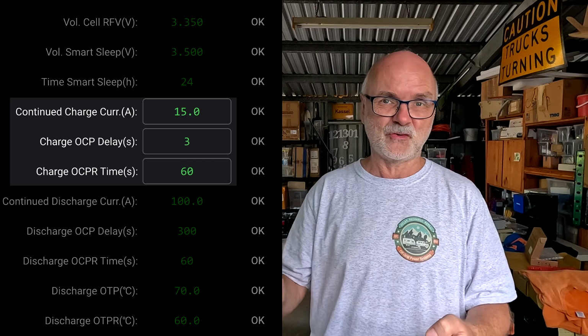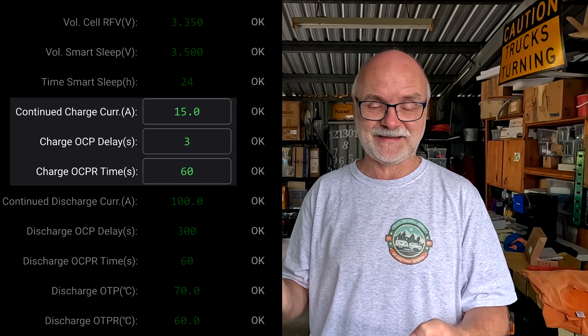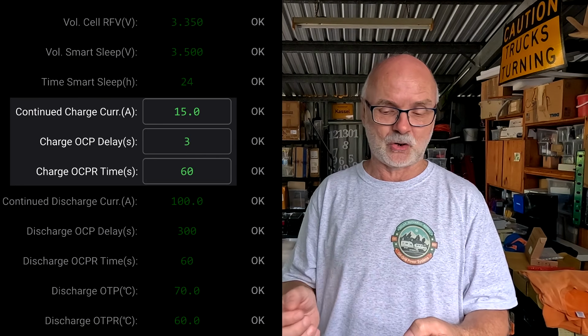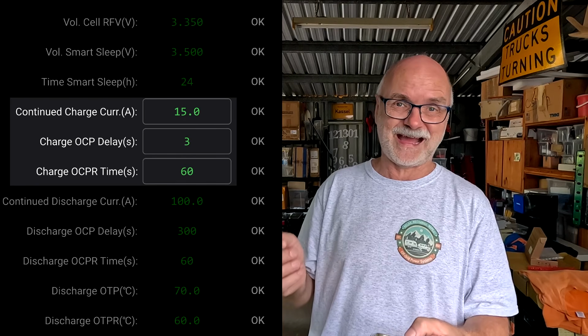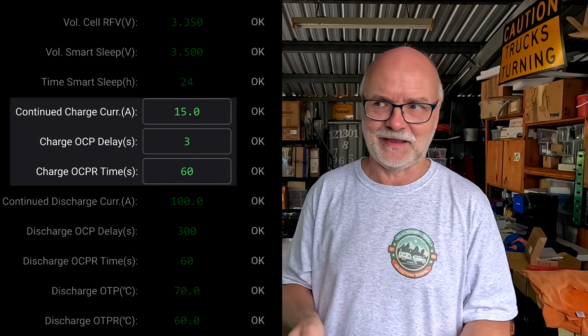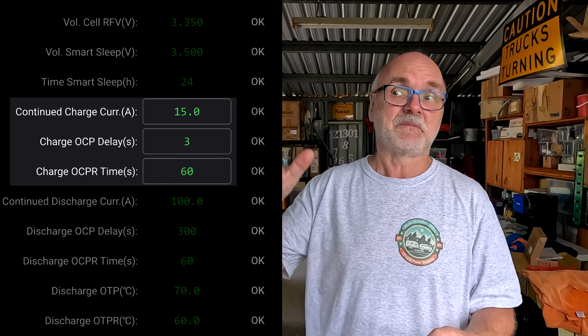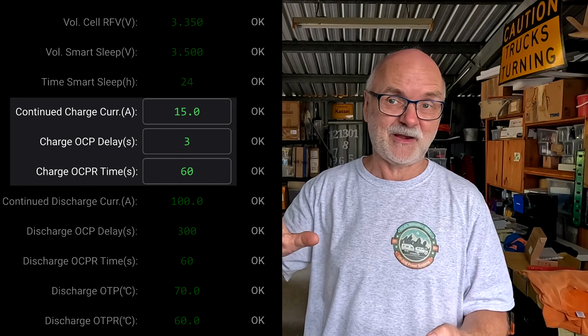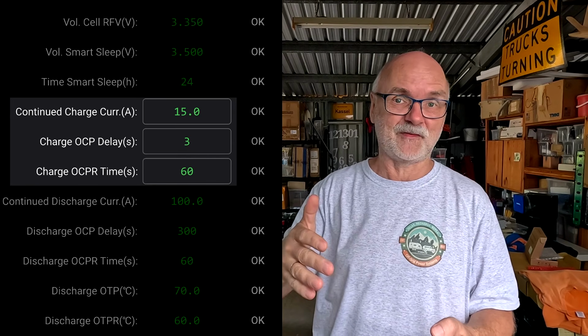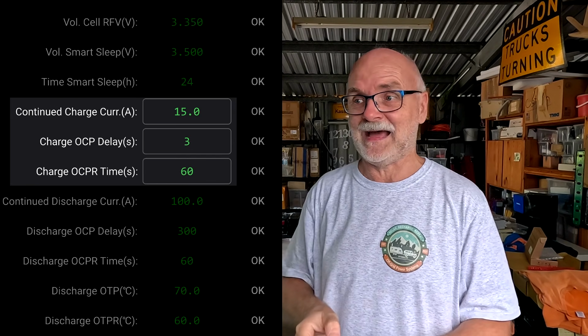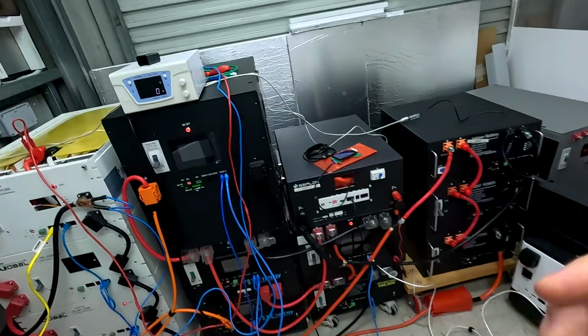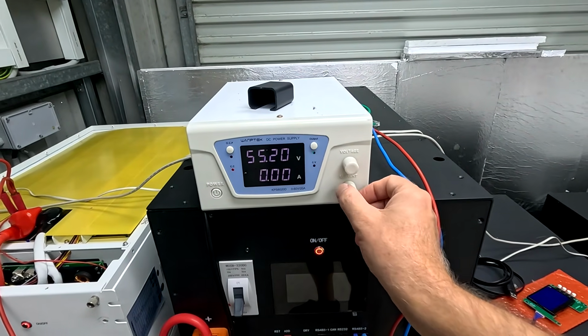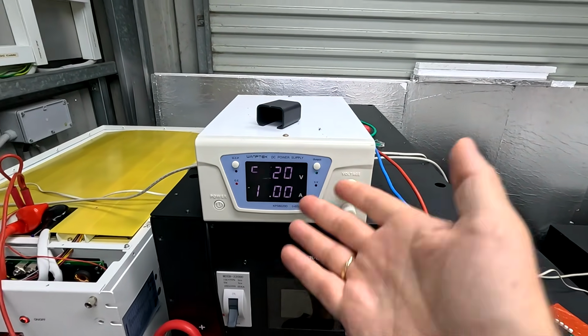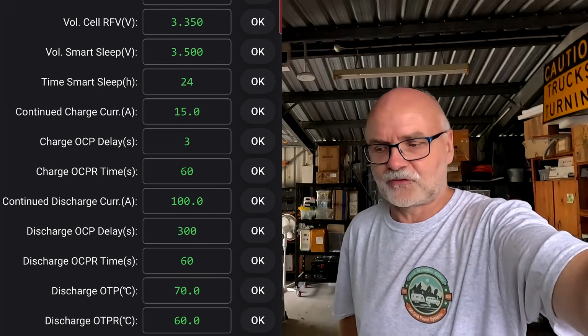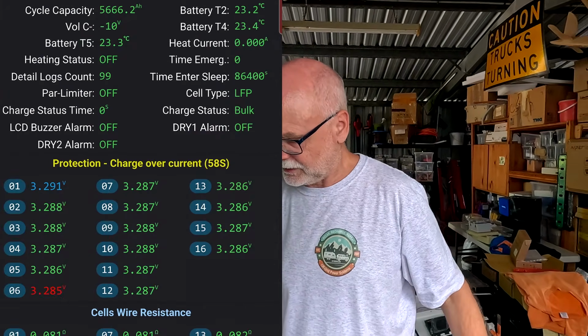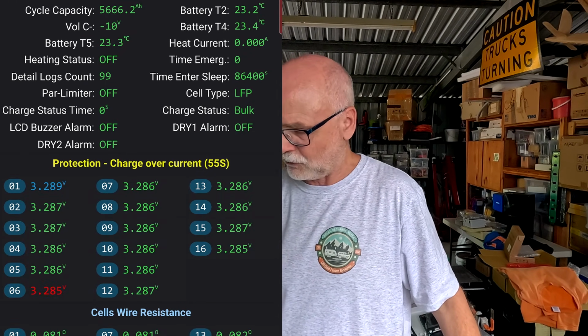Then we will go into alarm or warning for 60 seconds. Yeah, that means the charge over current protection recovery timer sits on 60 seconds. Yeah, for this 60 seconds, it will stop charging this battery. We've got an overcurrent. It turns off the MOSFETs and also sends an alarm here to the system, obviously. So let's give this a go. Change this here to, say, 18 amps. 1, 2, 3 seconds. And we should see here a protection charge over current.